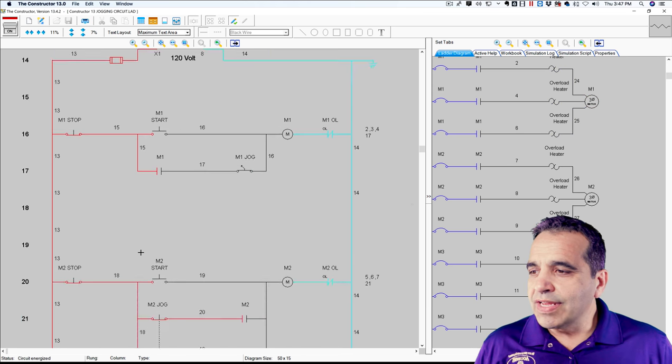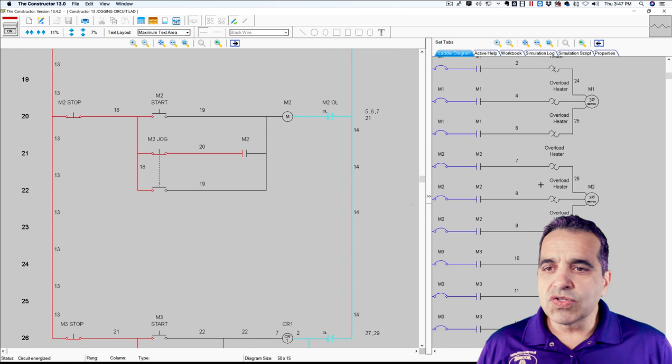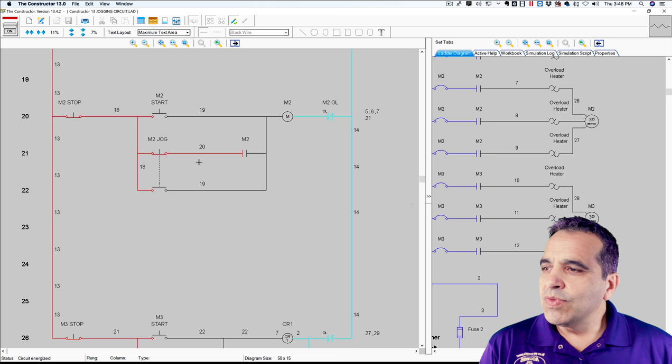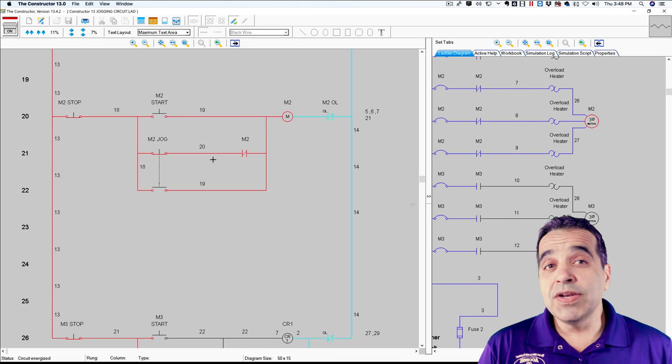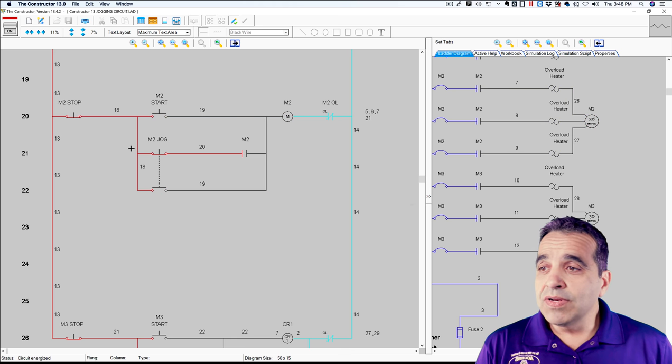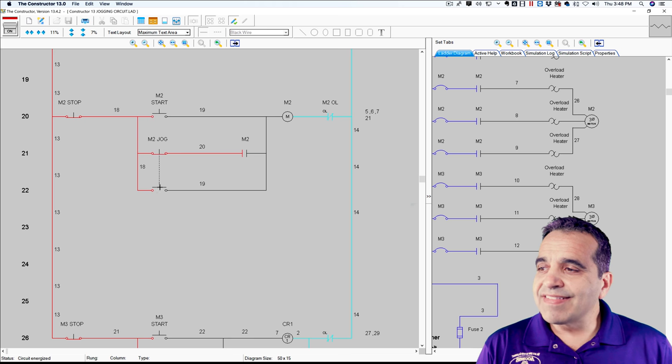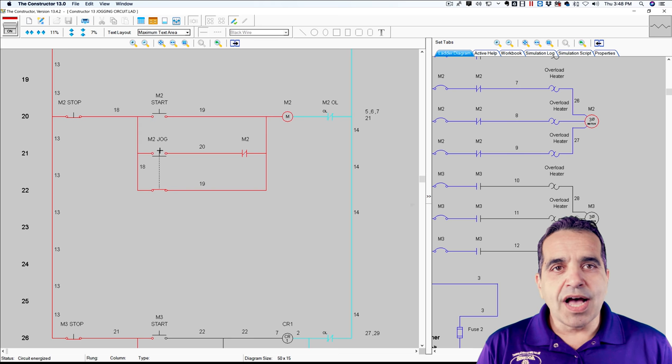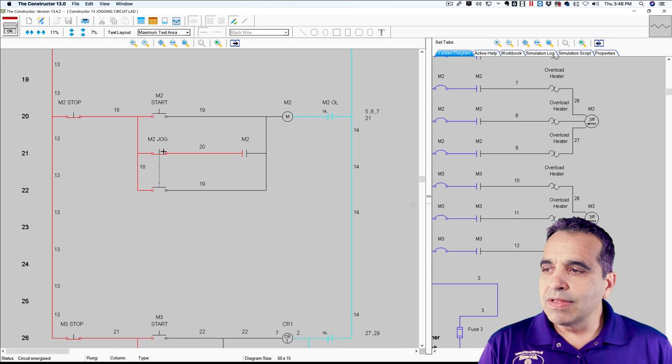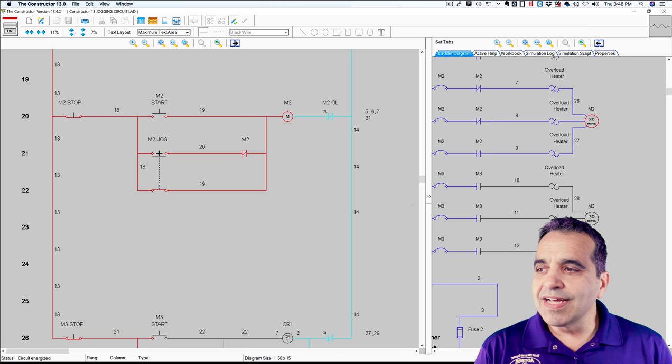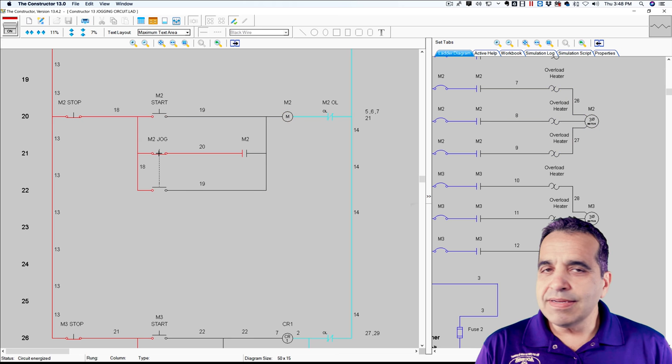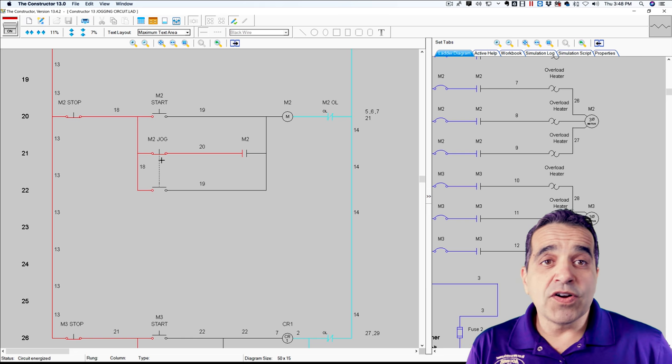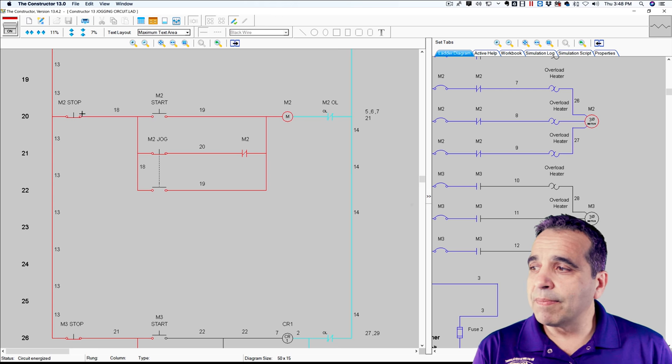Another way to do this circuit, let me just move on down. And now this circuit is going to control motor number two on this side of my screen. So it's going to control this motor. This circuit, I am using my start button as a start button only. My stop button also stops the circuit as well, but I have a separate push button that controls two sets of contacts. When you push the button, it's only a jog. It disengages power to my holding contact and acts as a jog. So I can jog the motor with this button and line that conveyor up or whatever using the jog switch. But when I take my finger off the jog switch, the circuit acts as a normal start stop.